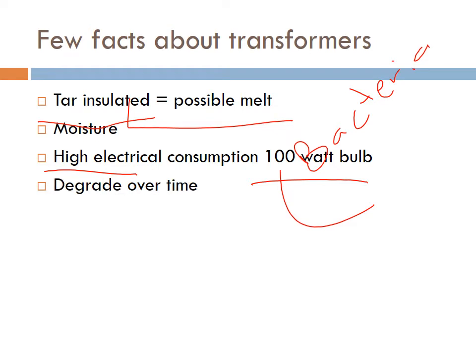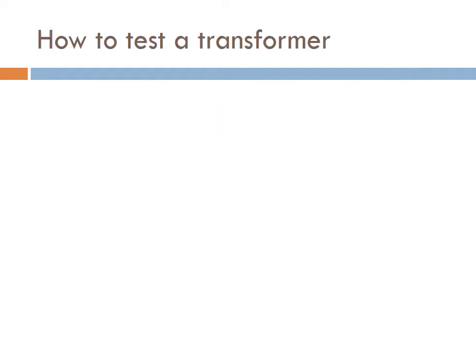They also degrade over time, and at some point the industry was leaning towards electronic ignitors, but they did not last as long. So everybody's going back now to regular wind-up transformers. But over time, with overheating, it will lose the ability to give you 10,000 volts. This is why we do this testing, to know if it's actually running correctly or not.